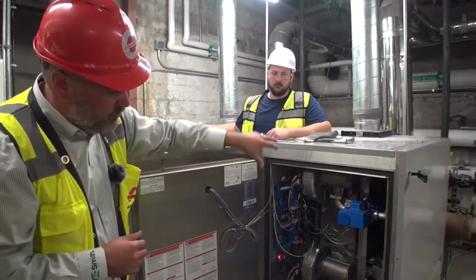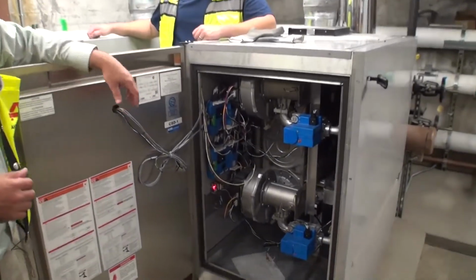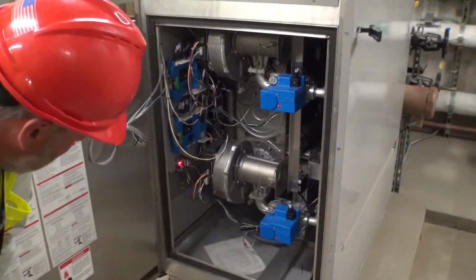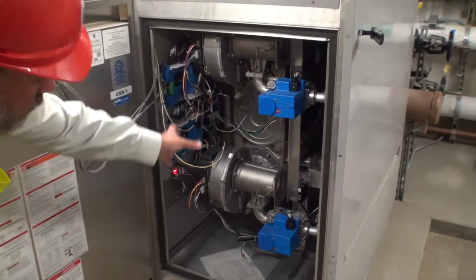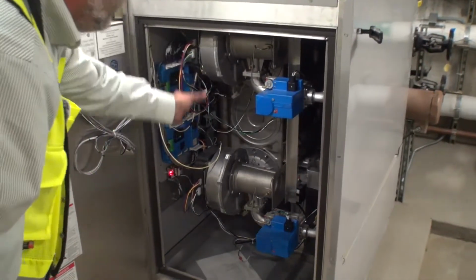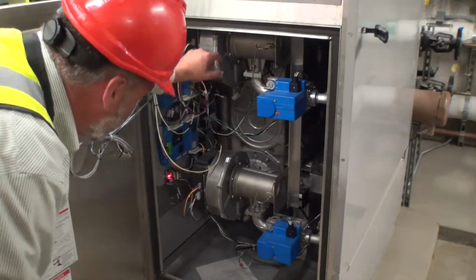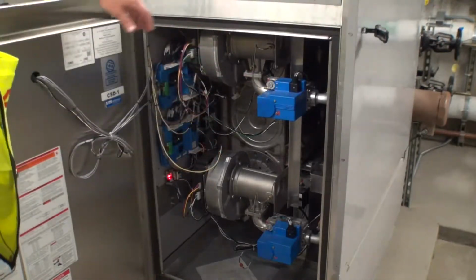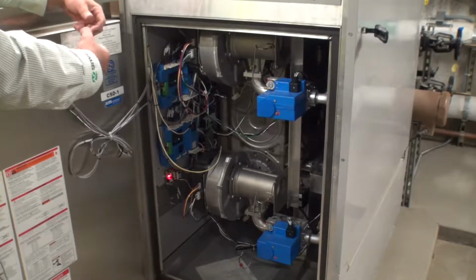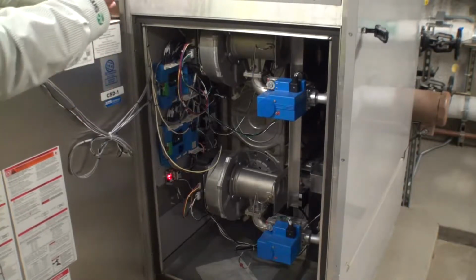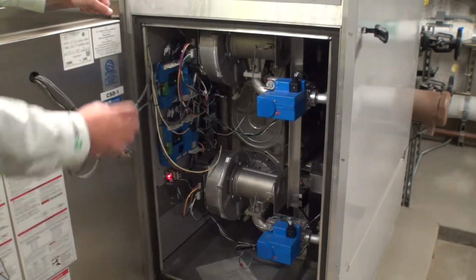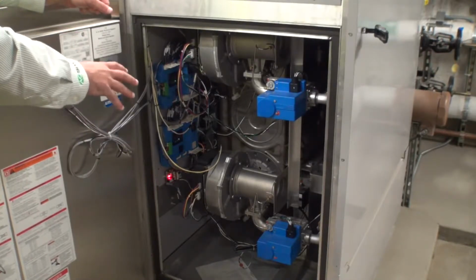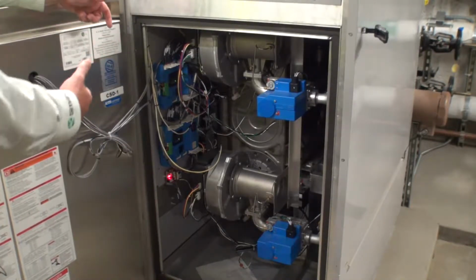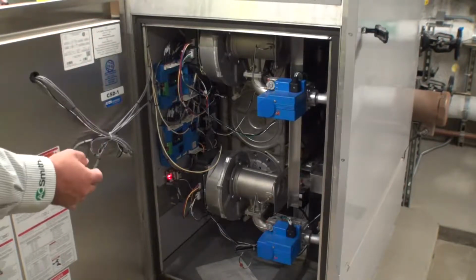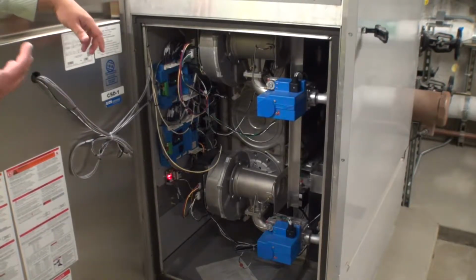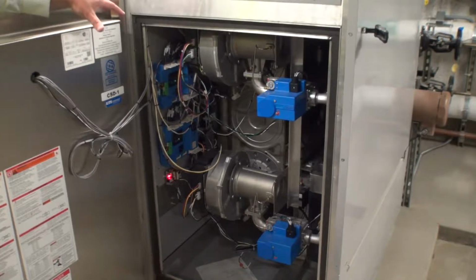A couple things to look at. I won't go too deep into this because it can be fairly technical, but you've got dual burner trains on here. So what that means is we've got our blowers down here, we've got our burners basically behind there. These are all operated independently and controlled. So if there is work that needs to be done on one of the burners, we can shut just that burner down and the other one's still operational. So even though we only have 2 burners on here, technically we have a 4-to-1 operation of this equipment.